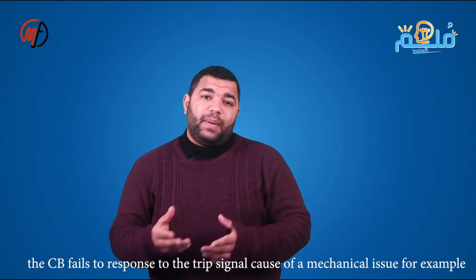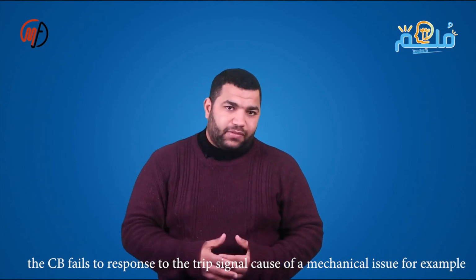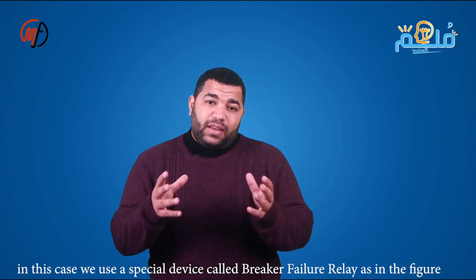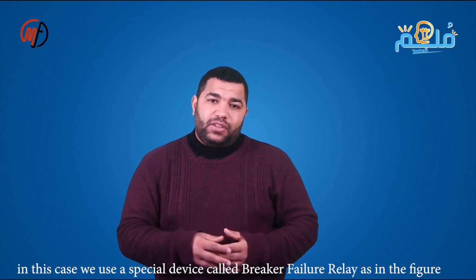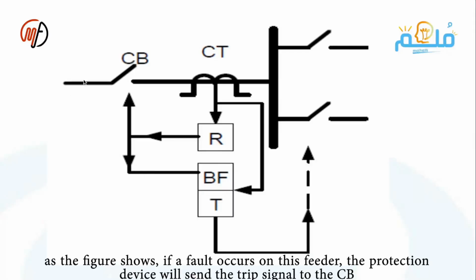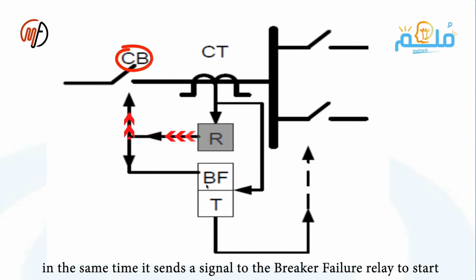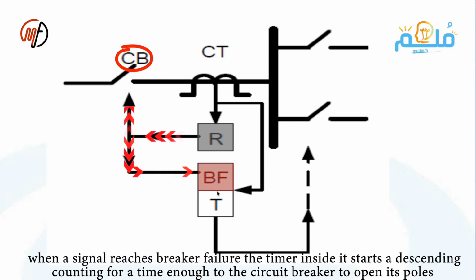The circuit breaker might fail to respond to the trip signal coming from the relay due to a mechanical fault, for example. In this case, we use a special device called a breaker failure relay, as shown in this diagram. If it encounters a fault on this feeder, the protection device sends a trip signal to the circuit breaker, and at the same time, it sends a signal to the breaker failure. As soon as the breaker failure signal is received, the timer inside it starts a countdown for a duration that is sufficient for the circuit breaker to completely open the circuit.